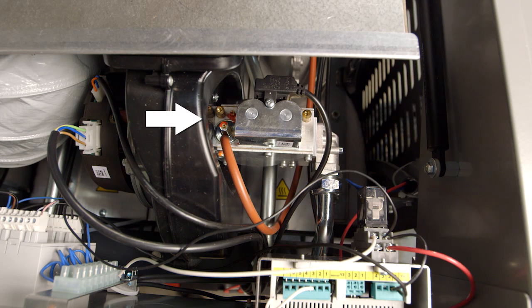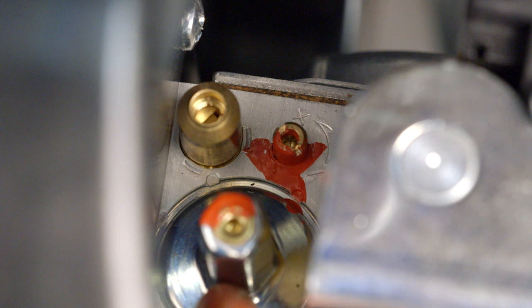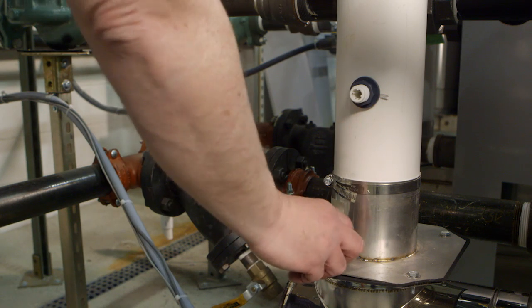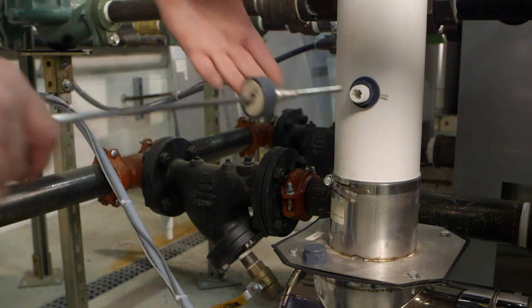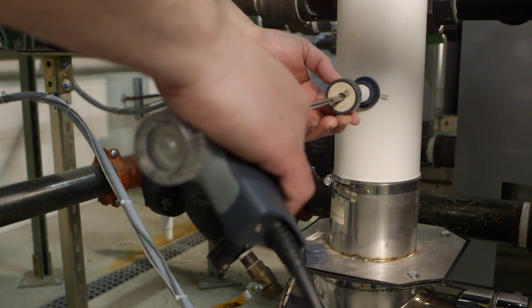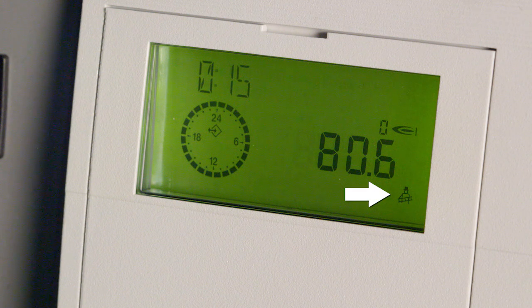Begin by locating the gas adjustment screws on your unit, as shown here. The screw indicated here is your maximum adjustment screw. It can be adjusted with either a small flathead screwdriver or a metric Allen key. As we instructed in the last section, remove the cap from the gas outlet as shown, then connect a gas analyzer. Enter manual mode on your unit.